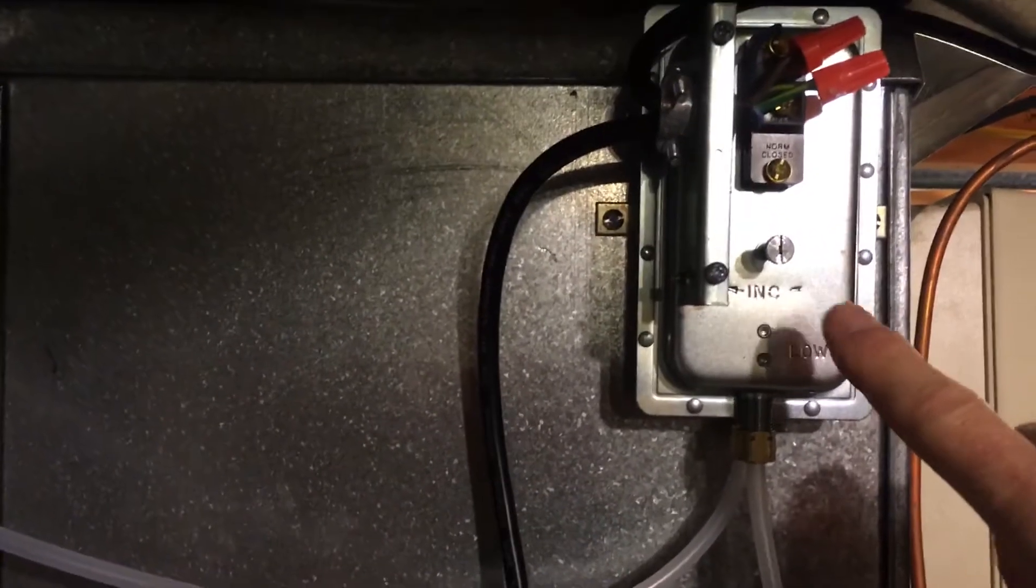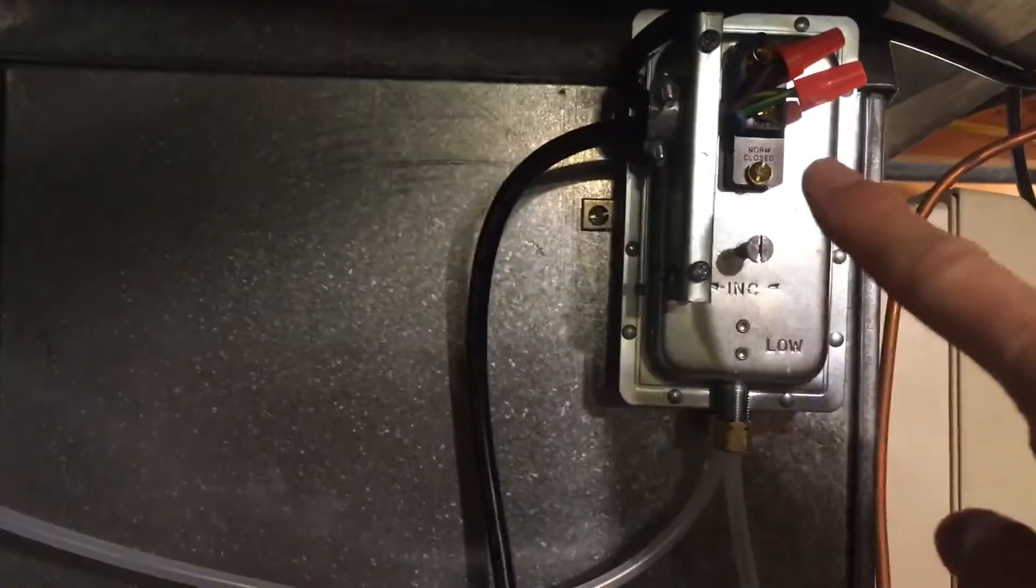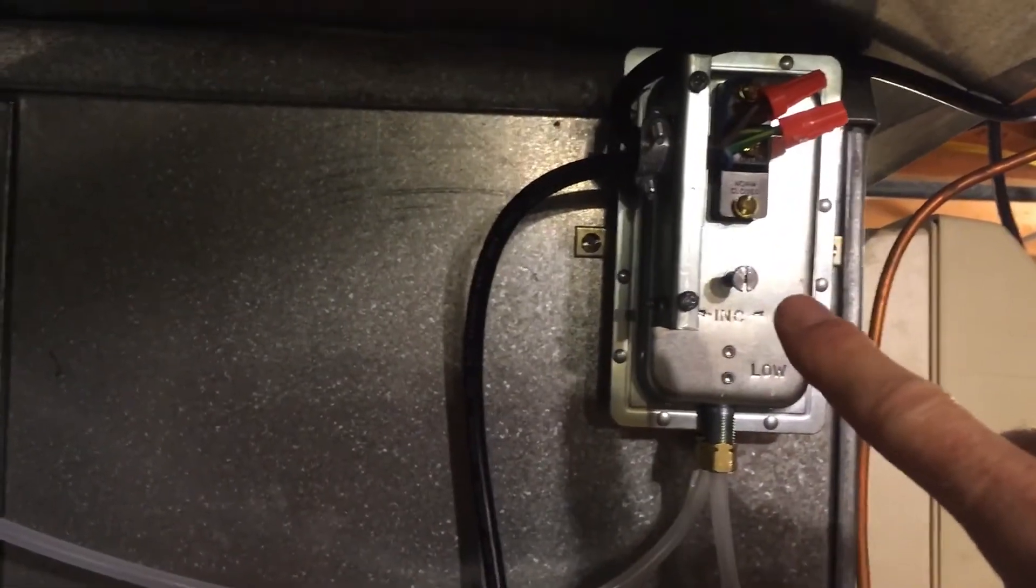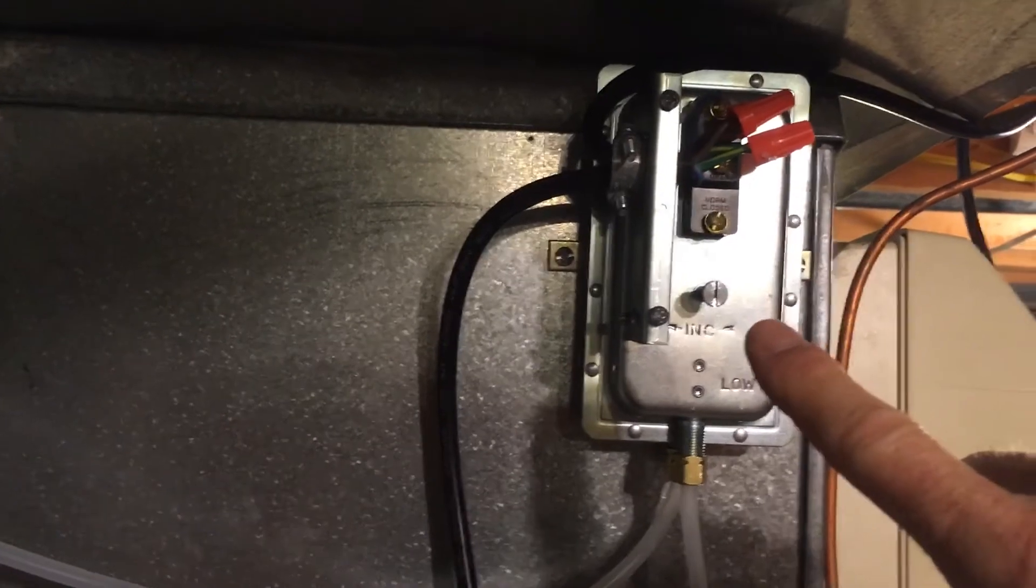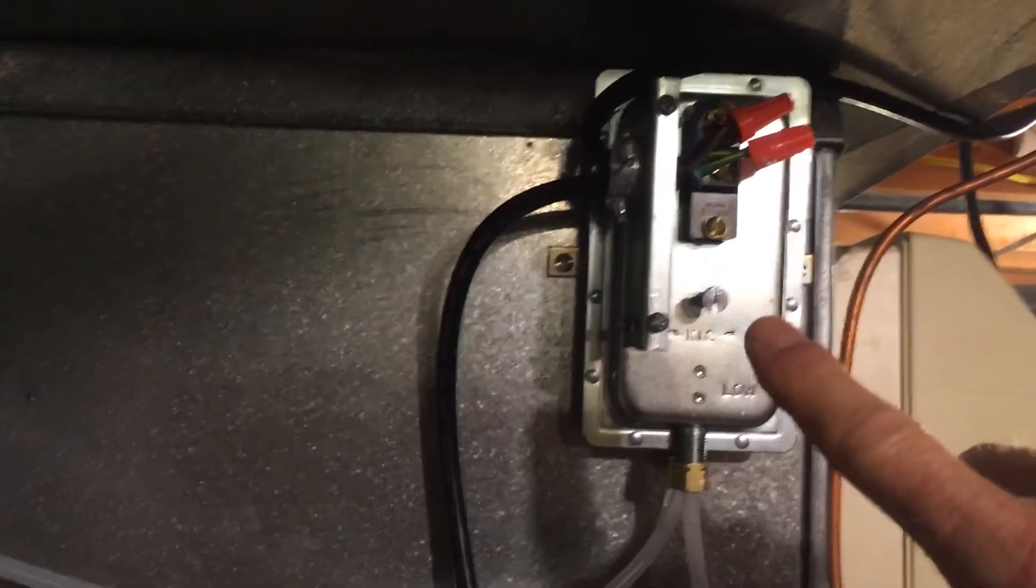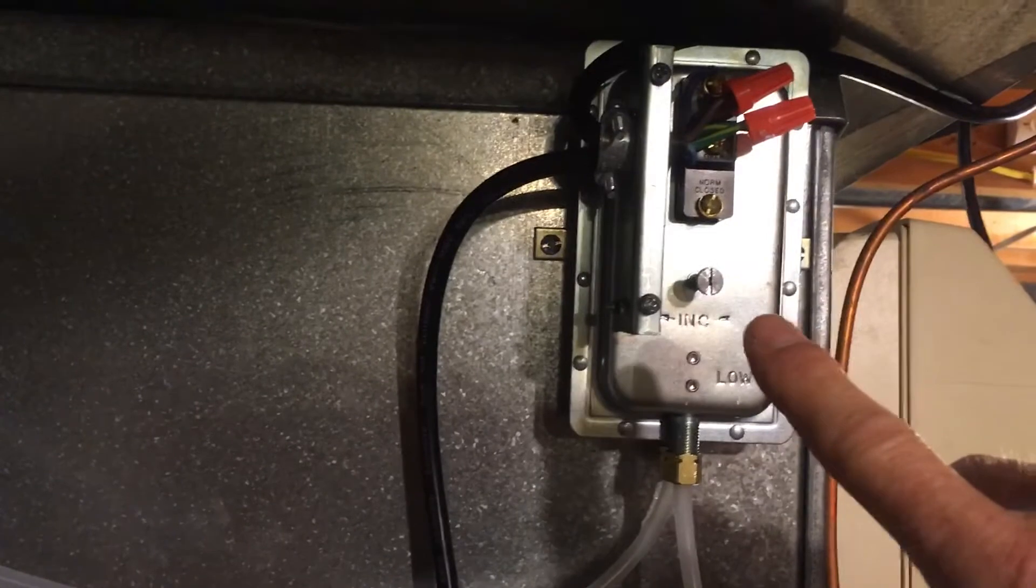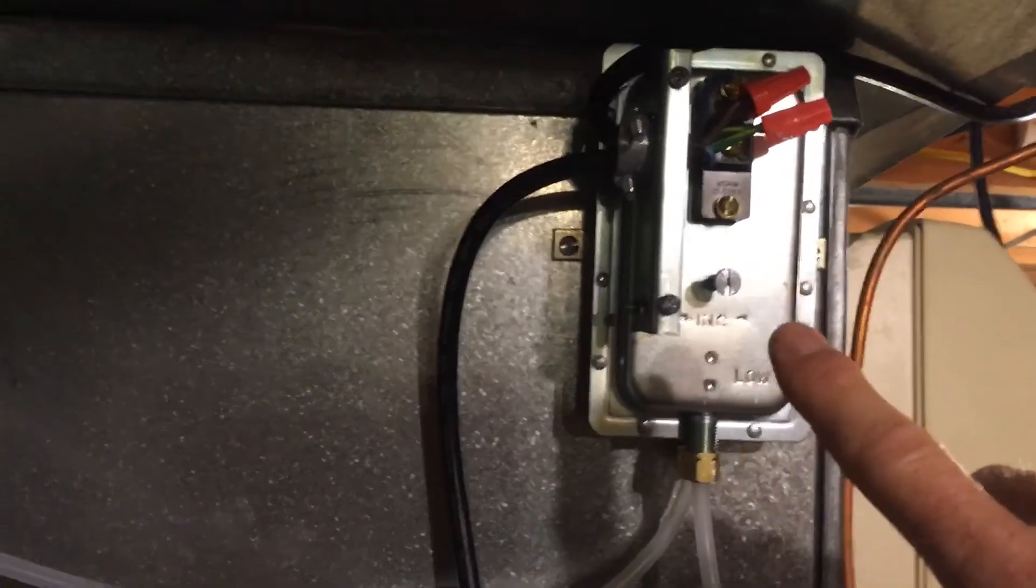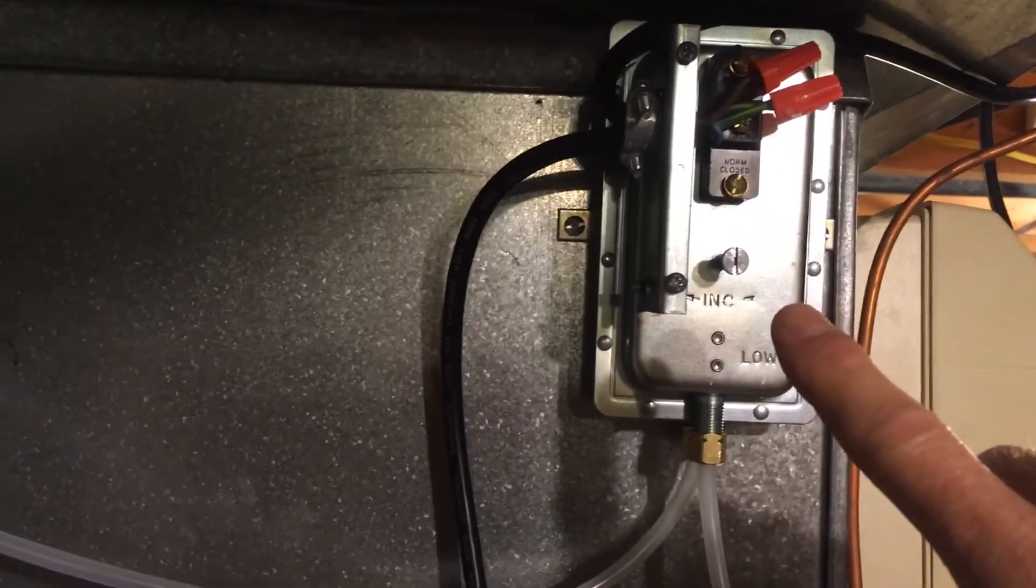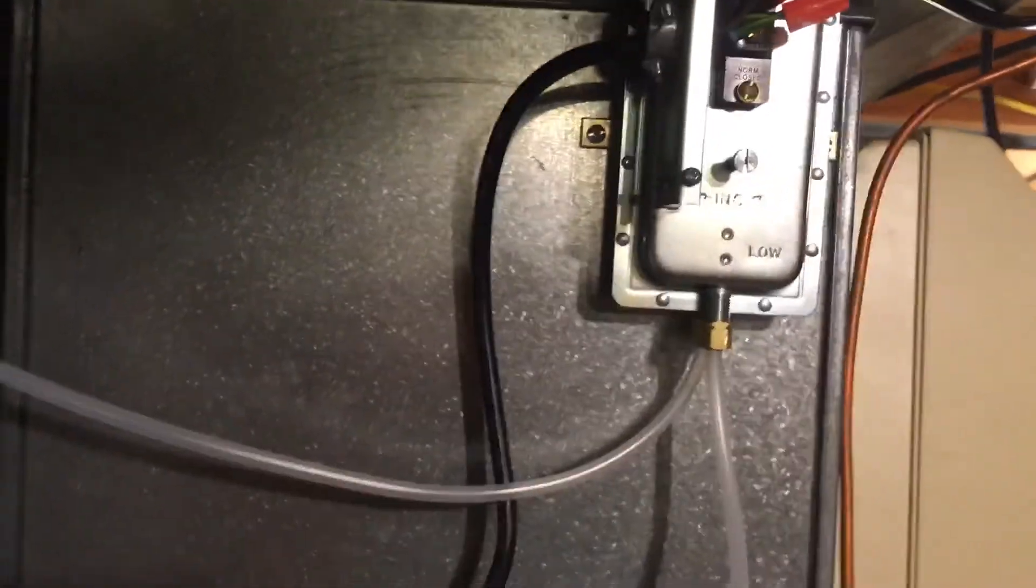Basically this dial, you turn it all the way counterclockwise to stop and then about four complete revolutions to the right gets you to about 0.02 inches differential pressure and that's probably your best setting right there, but you may have to experiment with it.